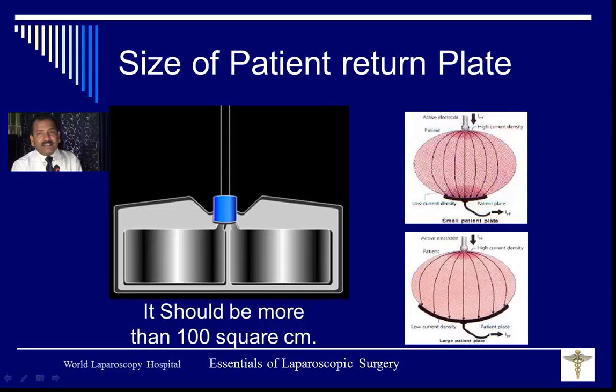If it is less than that, heat will be produced both at the place where you are touching and where your return plate is, and your patient will get burned. But if you have a big return plate, heat will not be produced there, and it will be only where you want. That way you can prevent remote injury. So, to prevent remote injury, proper application of the return plate is needed, less power should be used, less tissue should be held at one time, and intermittent activation is required. If you keep this in mind, there will be no remote injury.